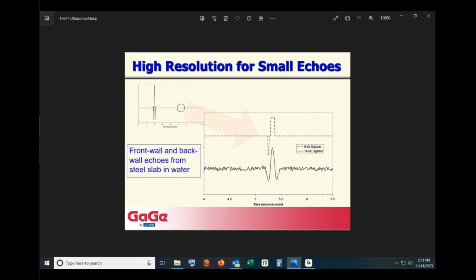You remember I had that knob on my ultrasonic pulser receiver. I can increase the gain of the amplifier, but I can't increase the gain any more than it already is here, because I would saturate this front wall echo. So I'm forced by the front wall echo to keep the gain at a certain amount. And that limits then, by the physics of the situation, the size of this back wall echo, which turns out to be only about 2 levels for an 8-bit digitizer.